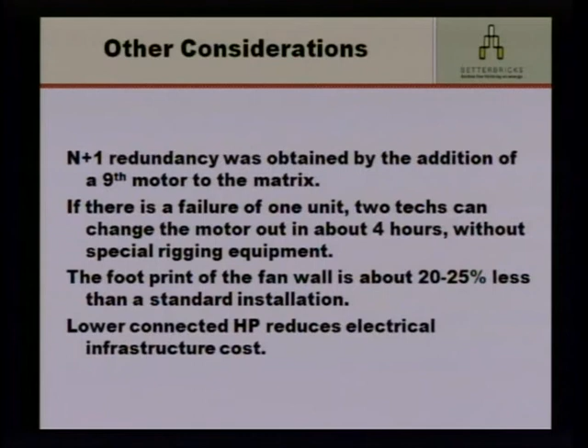By the way, there are a few other things. You got redundancy because if one of those little fans went out, it wasn't a big deal. They had a spare anyway. A technician can change one of those little fans if it goes out, literally by picking it up, taking it, and putting a new one in. No crane, no special rigging. It's a smaller footprint, and it reduced their electrical infrastructure costs for wiring because it's lower load.